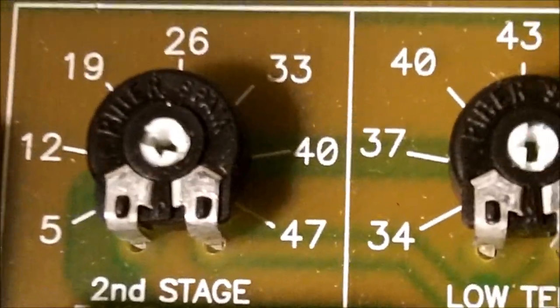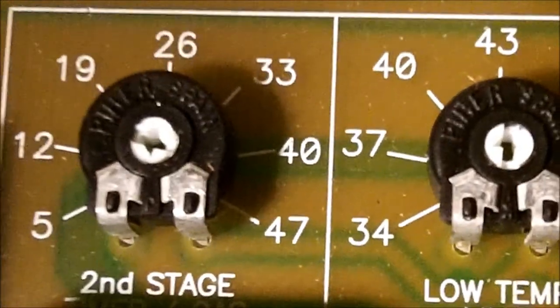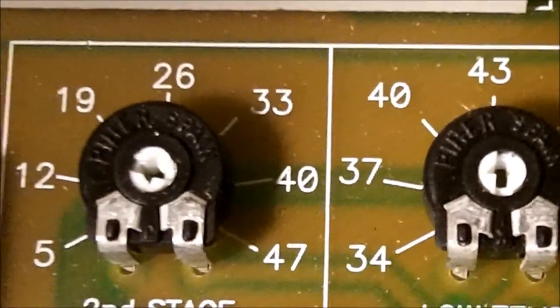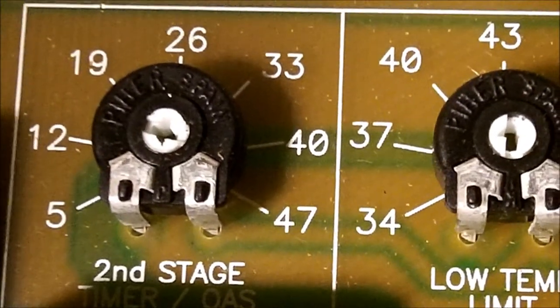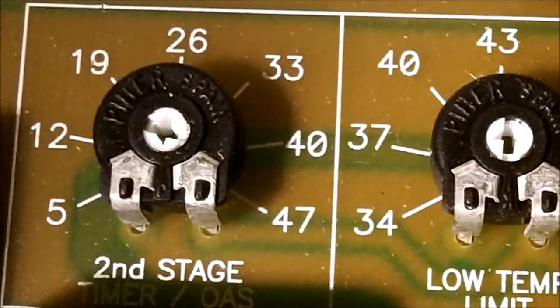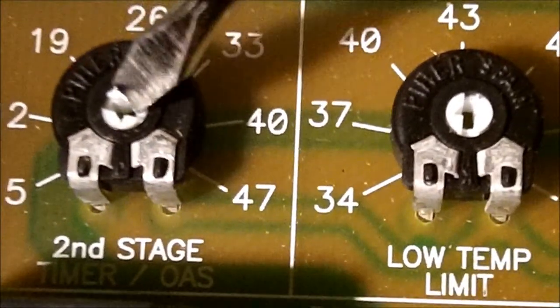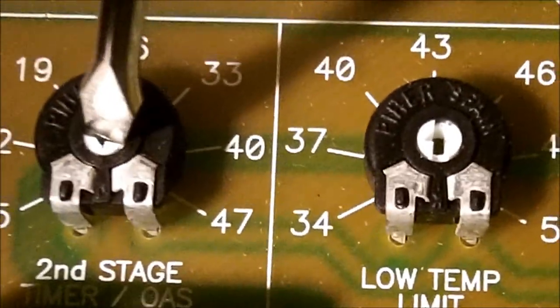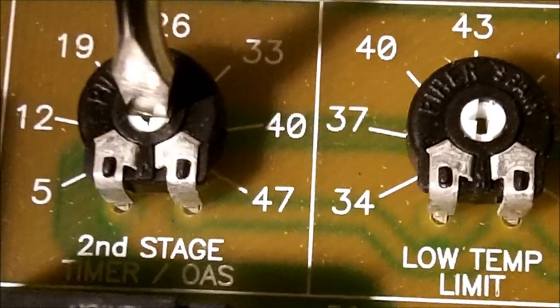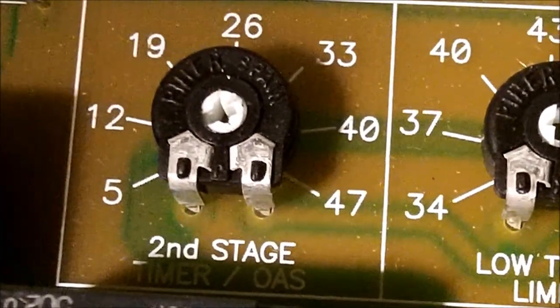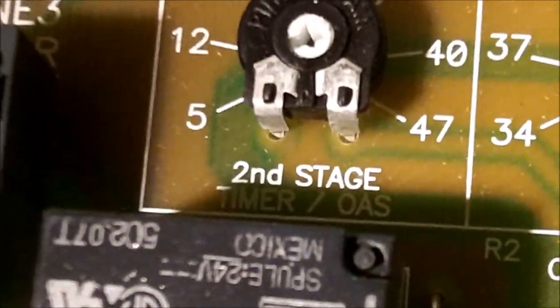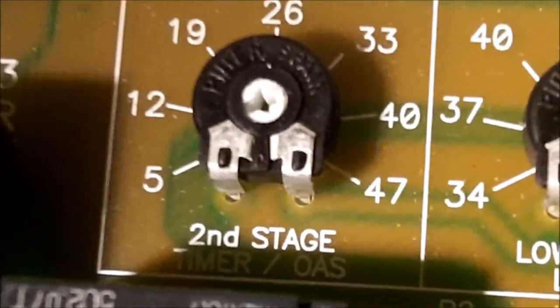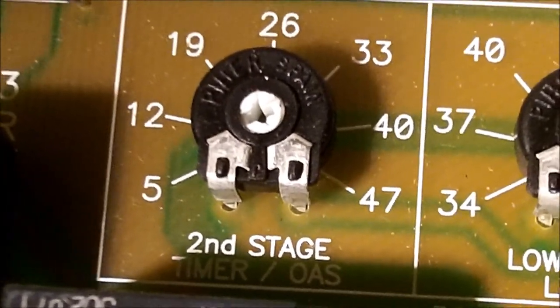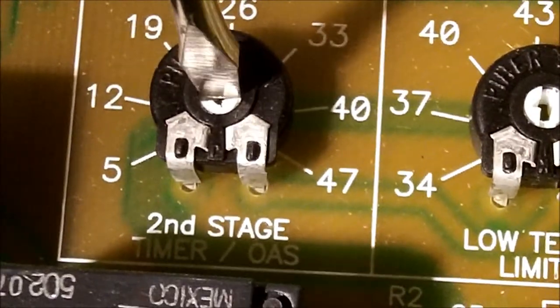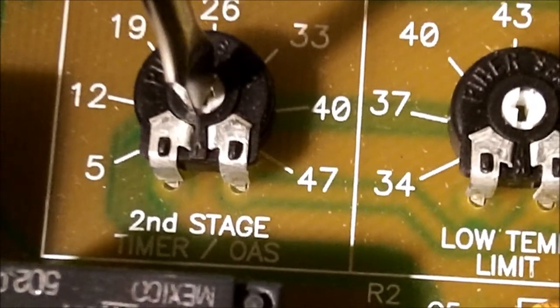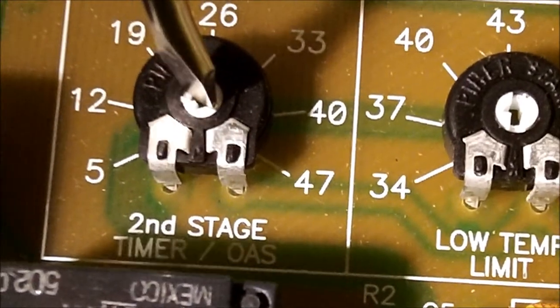If you have an outdoor sensor, it means you have a heat pump. If you just have a regular air conditioner, you wouldn't put the outdoor sensor in that application. So if you had a two-stage air conditioner, you would use the first dial here to set your time, set your staging. So 5 minutes, 5, 12, 19, 26, 33, 40, and 47. That's your minutes or your temperature, depending on which one you use. And I'm going to set it up real high, because I'm going to show you the operation of the outdoor sensor in just a little bit.